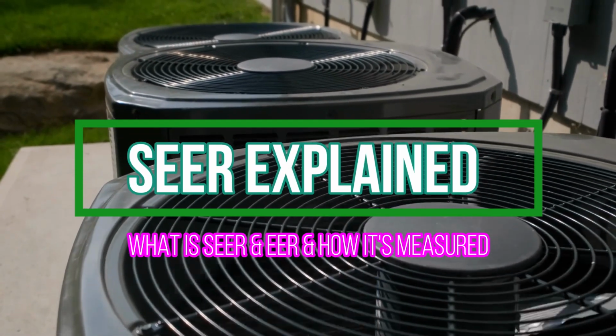So a piece of equipment was being rated at 0.1 inches when they did the test and they were doing their ratings. That was not real world. When we got out into the field, a half inch or more is what we usually find when they actually got installed. And so they changed it on January 1st, 2023 to a half inch that they rate this equipment now. They rate it at real world conditions most of the time, so it's more accurate.